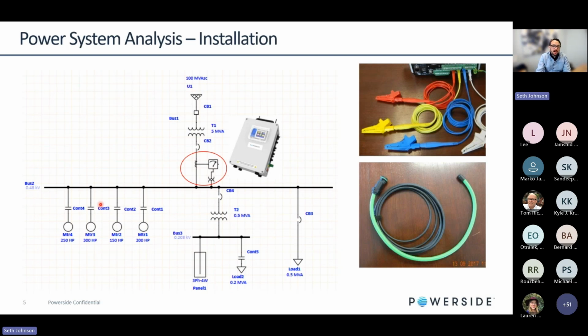We can certainly look downstream at some of these loads. But again, a lot of what we're doing for the analysis is to make sure that we're meeting compliance standards for things like power factor, voltage imbalance, harmonics, things like that. And so making sure that we're looking at the entire power system is really the idea behind this program.